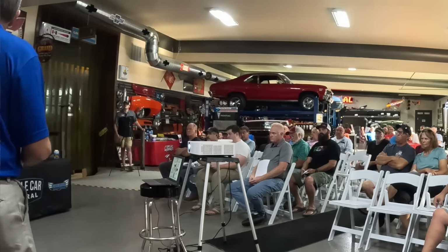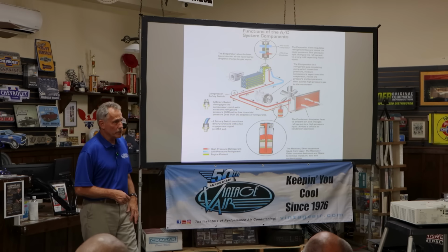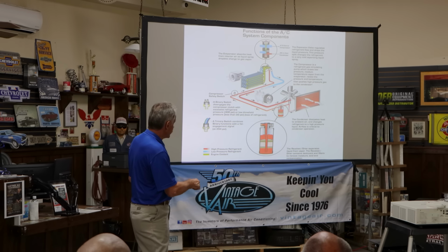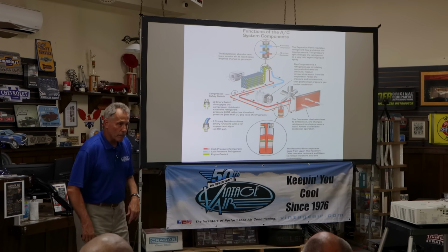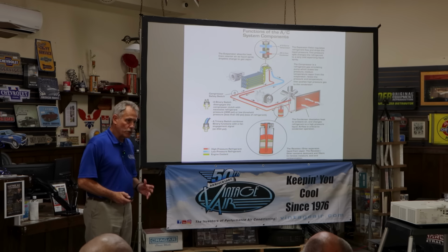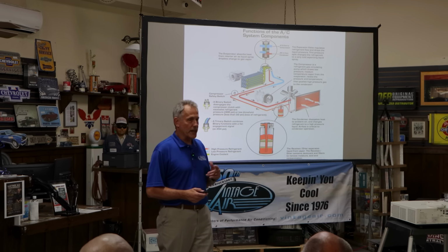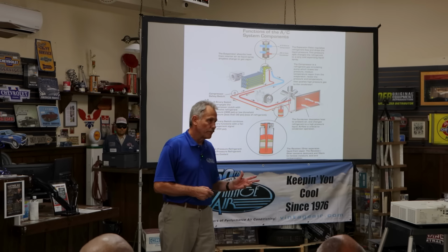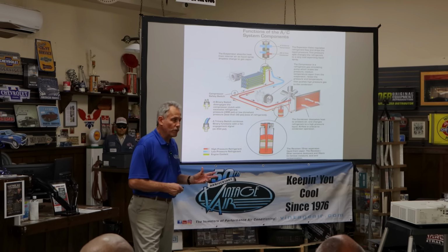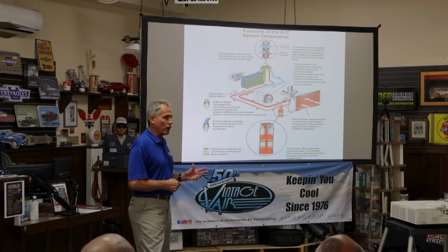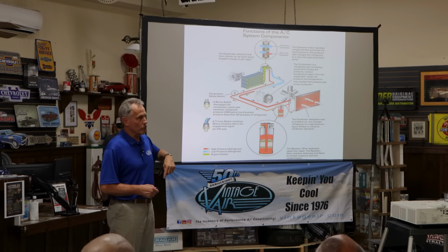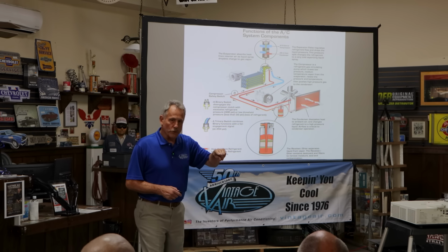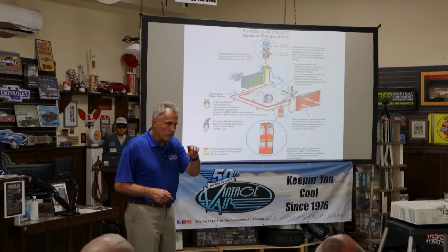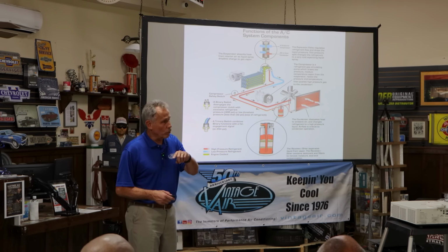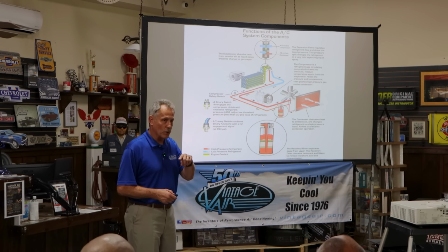Okay, continuing to talk about our system operation a little bit here too, all right? The next component of the system we need to talk about is the compressor safety switch. All right? A compressor safety switch protects your compressor from damage and protects the rest of your system from damage. And again, we just talked about how oil circulates throughout the system in suspension with the refrigerant. So if we lose refrigerant, what else do we lose? Oil, right? So if we lose oil, things without oil don't run good. Any moving parts without some kind of lubrication.